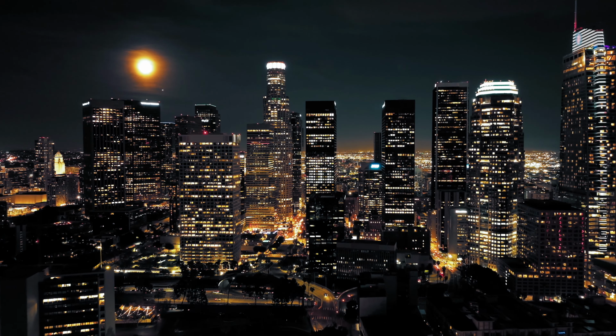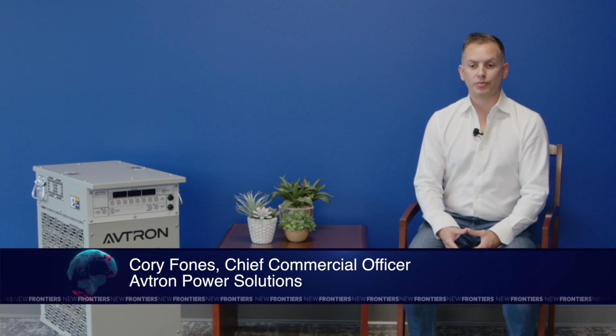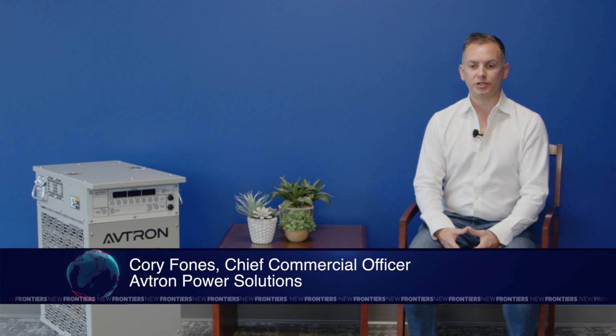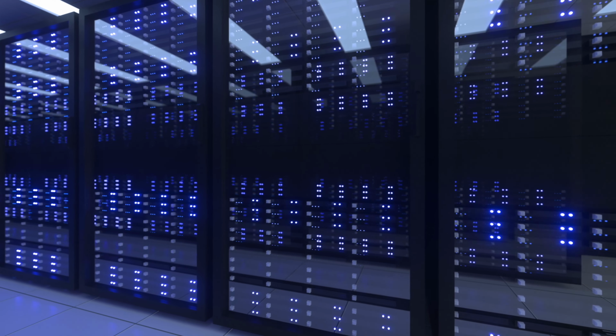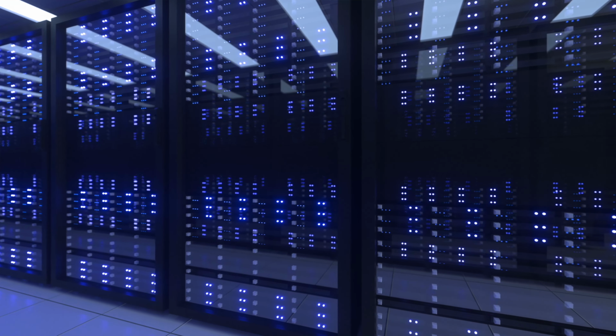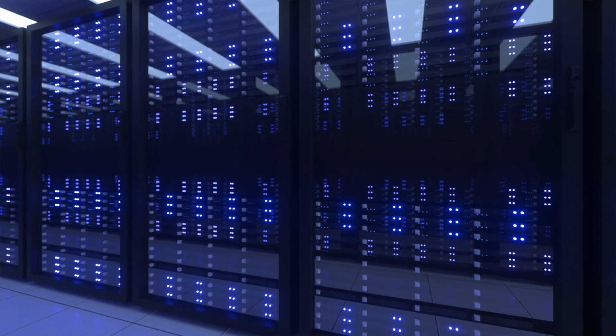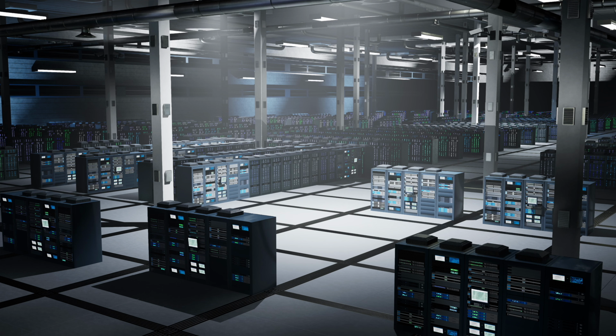What we're seeing in the industry is that the data center market is really in a paradigm shift right now, changing drastically with the introduction of AI into the space. Where they were traditionally building data centers at 40 kW per rack, now we're seeing 120 kW being constructed per rack. With that level of density in a small space, air becomes not efficient enough to cool it, so they're now introducing liquid all the way down to the chip level in these racks to cool the servers.